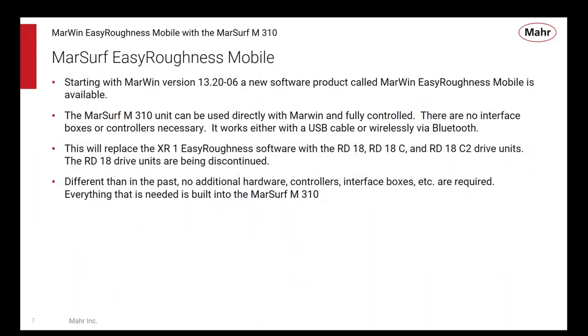So what is Easy Roughness Mobile? It's a new software package that is just available starting last month. With the Easy Roughness Mobile software, you can control this mobile MarSurf M310 directly. You can control all aspects of how it's used. It basically becomes just a drive unit for the PC-based software, and you do all your analysis and calculation of parameters and filtering and all of that on the PC. This replaces, for those of you that know our product line pretty well, the XR1 Easy Roughness software and the drive units RD18, RD18C, and RD18C2. All of those are being discontinued and replaced by the M310 family of drive units.